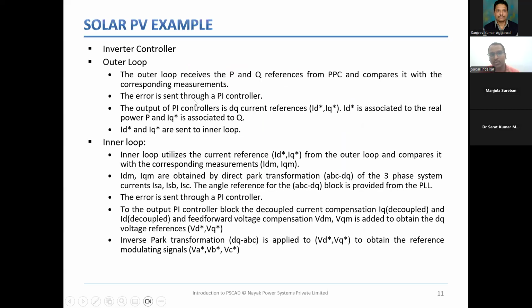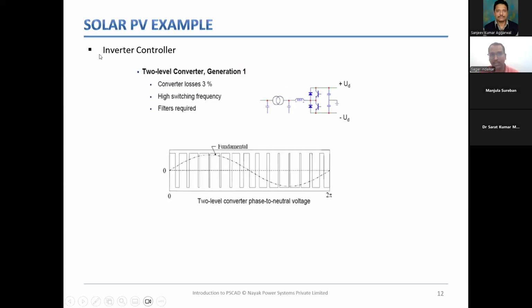So your inverter will have an outer loop, which will follow the P and Q command. It will try to reduce the error between set points and measurements. Your inverter control will generate voltage references to obtain that ID and IQ. Ultimately, those references VA, VB, VC will be given to a PWM circuit like this. It will generate pulse width modulated waveforms, ultimately resulting in your AC side voltage.